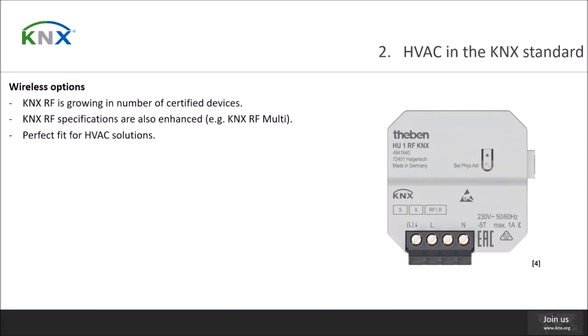Wireless options: it's not a secret that KNX has been mostly present with twisted pair devices for many years. Luckily, it has been in the market for more than 30 years. But wireless options are growing, and KNX RF is a very good option, especially with the new release, or the upcoming release, of the ETS6, where KNX RF multi is supported. KNX RF multi contains 5 channels for communication instead of one, which is not the current scenario. So with the ETS6, you can directly communicate with this type of devices.